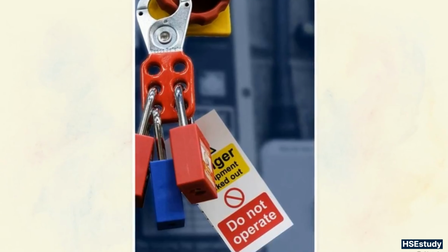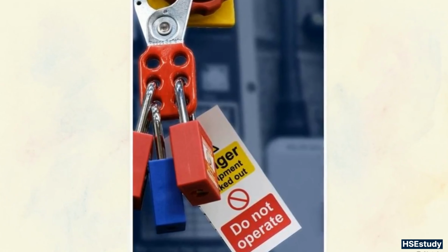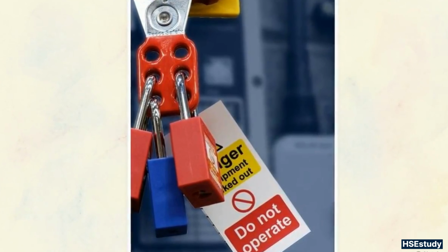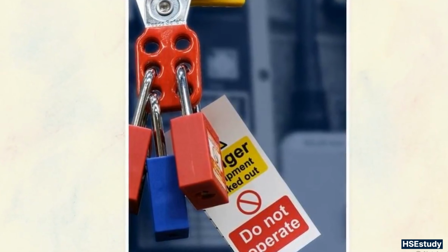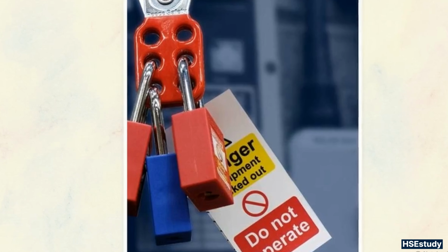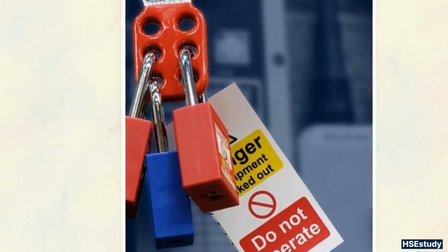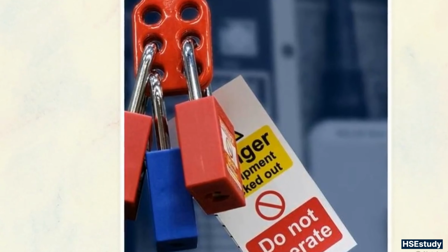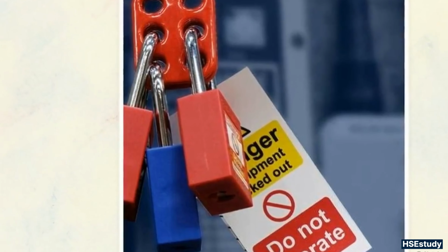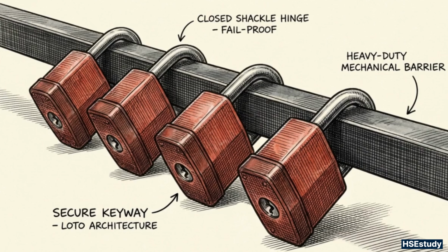When tasks require multiple workers, a group lockout is utilized. A Hasp allows every exposed person to apply their own lock, ensuring the system cannot be energized until the very last worker finishes their task and removes their key. A robust LOTO architecture relies entirely on impenetrable mechanical barriers and physical locks. It completely removes human memory, assumptions, and convenience from the safety equation.